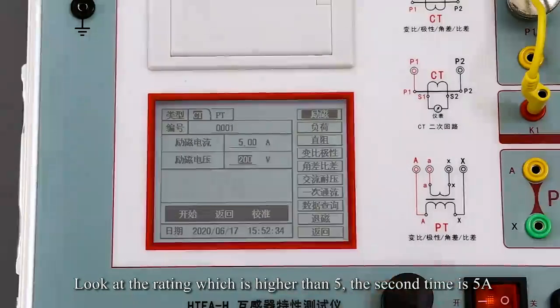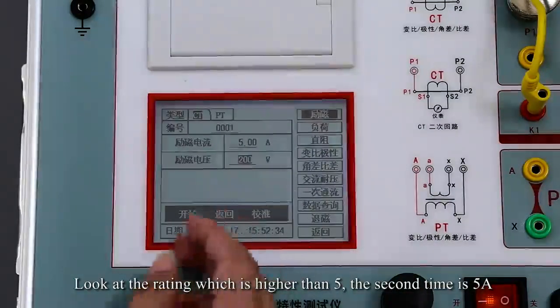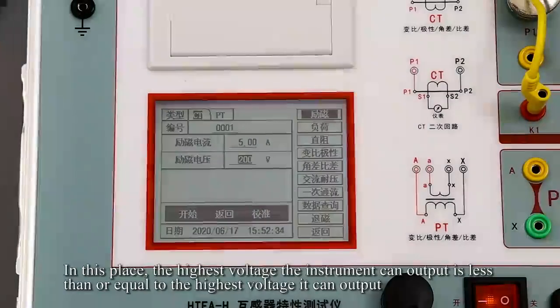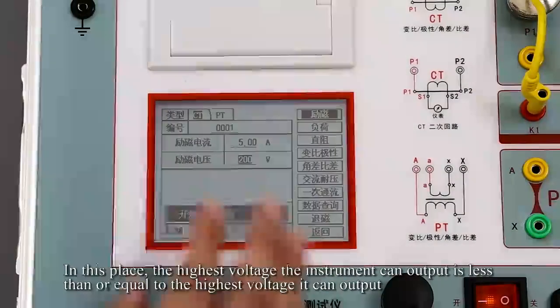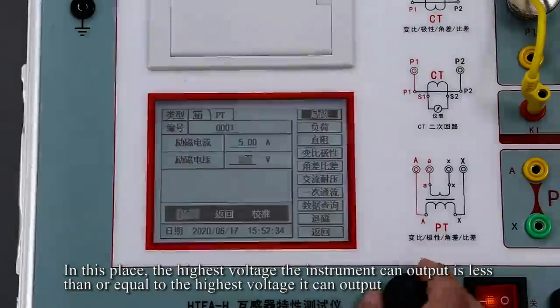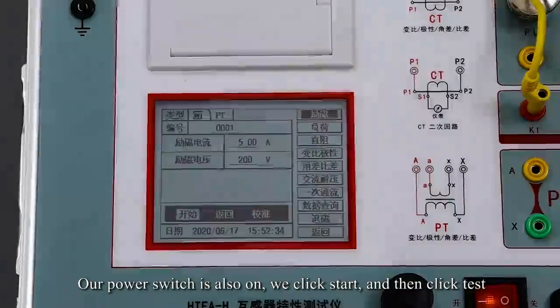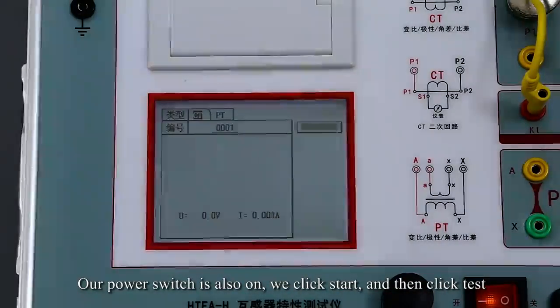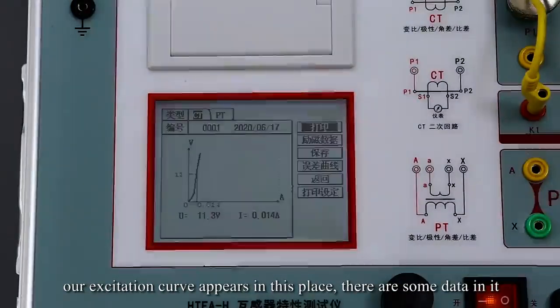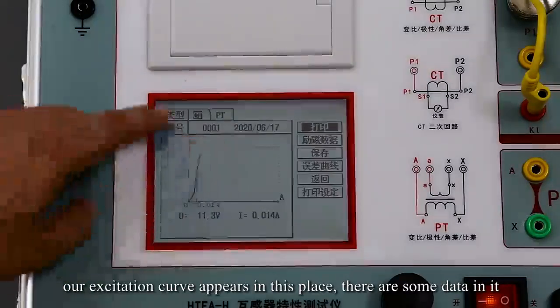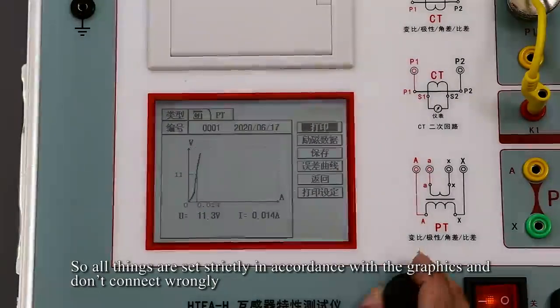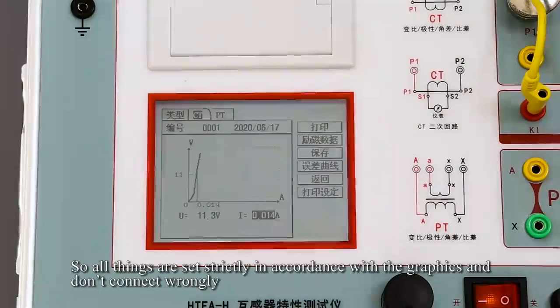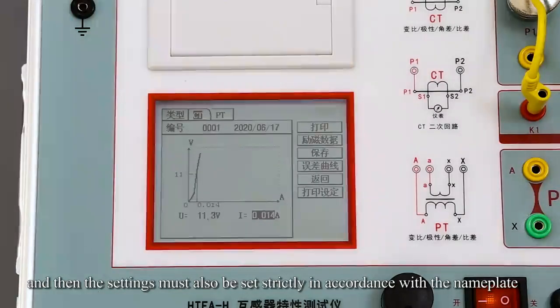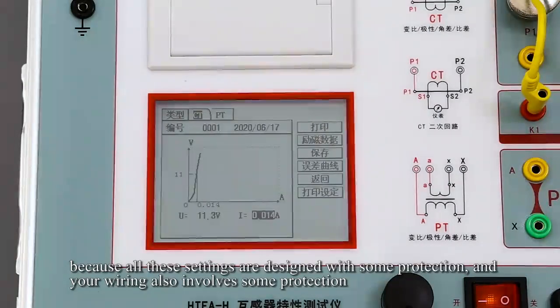Look at the rating, which is 5, and the secondary is 5A. In this place, the voltage we set must be less than or equal to the highest voltage the instrument can output. Our power switch is also on. We click Start and then Test, and our excitation curve appears here with some data in it. So set everything strictly in accordance with the graphics and don't connect wrongly. The settings must also be set strictly in accordance with the nameplate, because all these settings are designed with some protection, and your wiring also involves some protection.